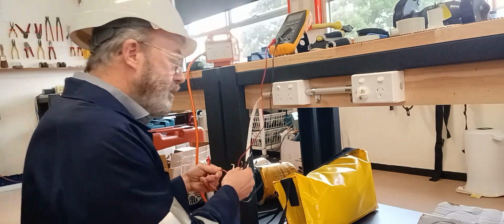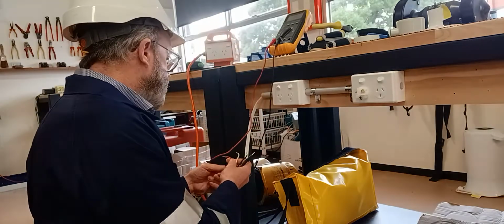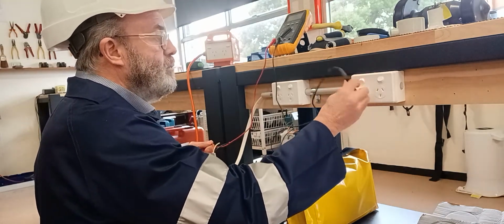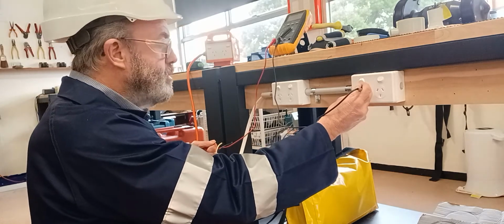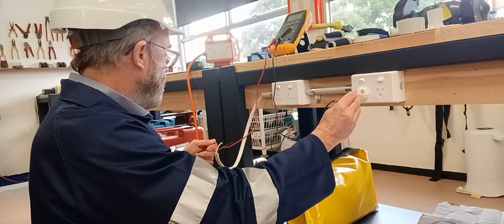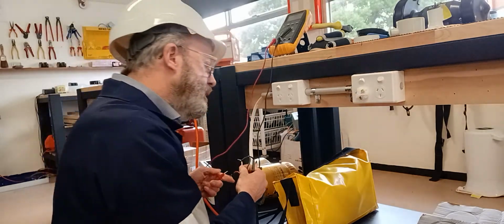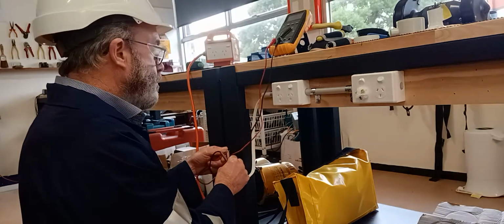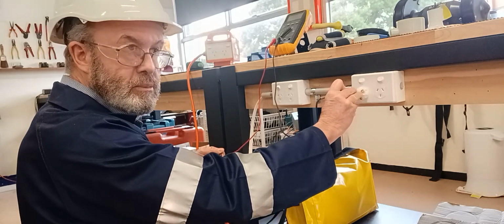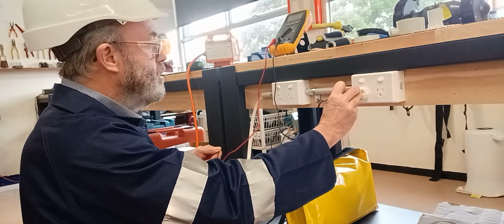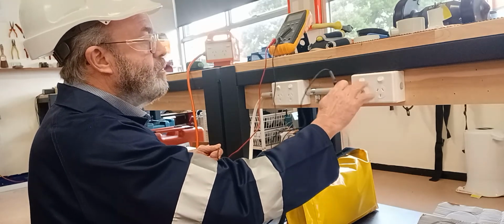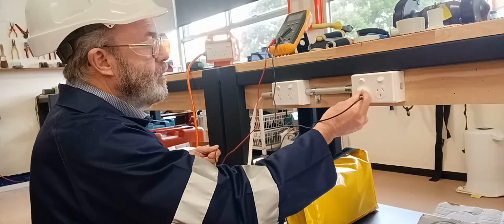So the first test is the active to the active pin. Okay, try that, there's no noise, turn the switch on, and we hear the noise. While I'm there, I just confirm the other 2 pins are open circuit. Now my next test is the neutral to the neutral pin, which is the black wire. Do the same again. I'll turn the switch off now. See that the switch has no control over that, so that's now reading a closed circuit, and therefore the noise. Test the other two wires. Test with the switch on, other two wires, and it's open circuit.